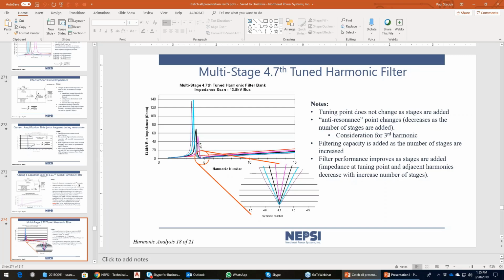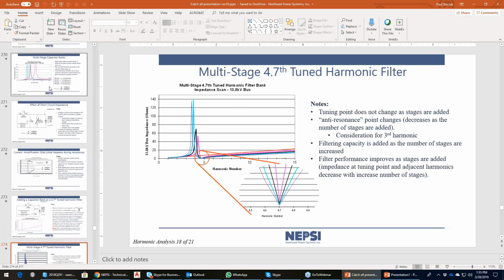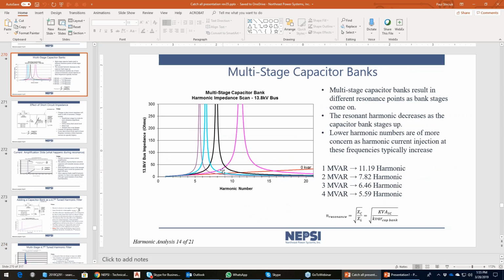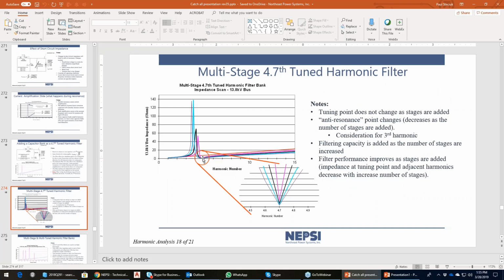Below the tuning frequency, though, you can see there's a resonant point that does exist, and that's created by the filter bank and the system impedance, and that does move. This is not of concern here because, generally speaking, there's no harmonic currents at a frequency below the 5th harmonic. So capacitor banks will cause resonance here at various frequencies. Those resonances would result in high voltage distortion and high current distortion in the system. When it's a tuned filter like this, you're going to push your resonant point down below your tuning frequency, and this is one of the key reasons why you tune to a low frequency, to avoid any kind of resonance above that tuning point. So we always start at low frequency and work our way up from there.